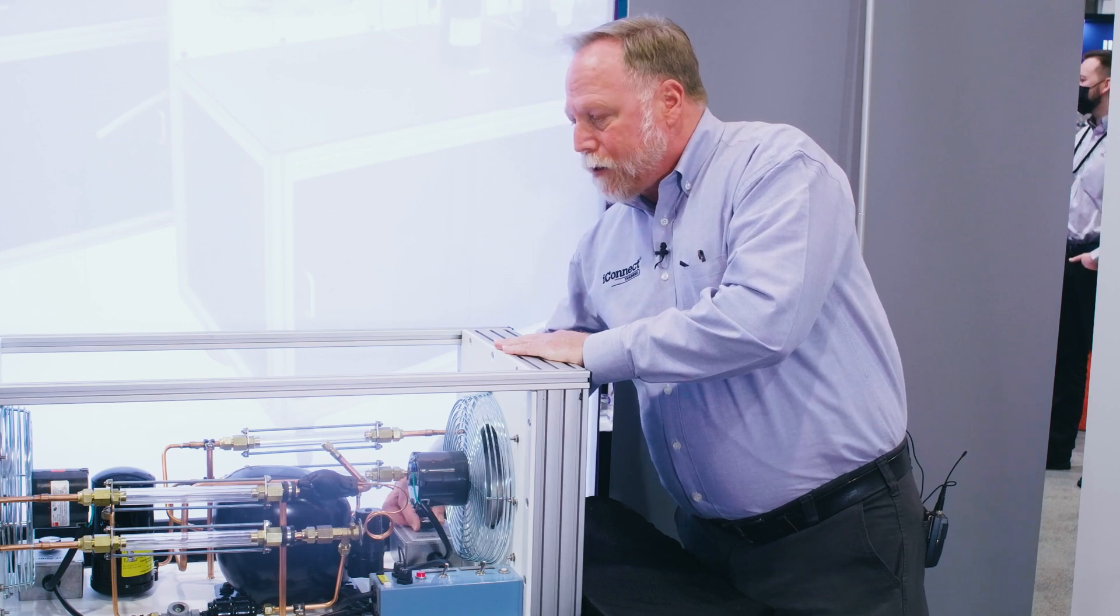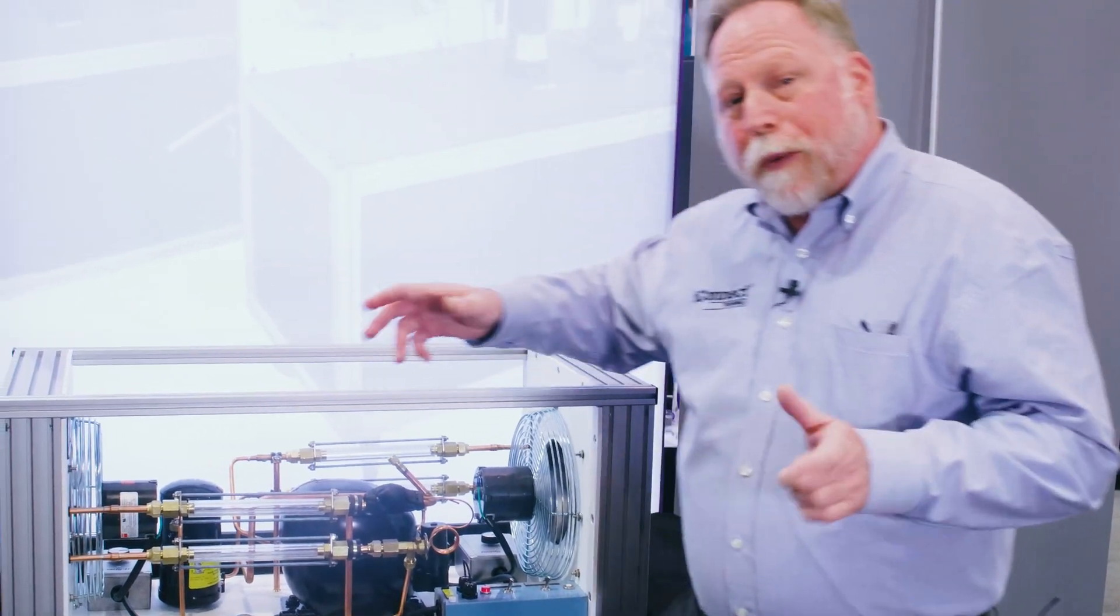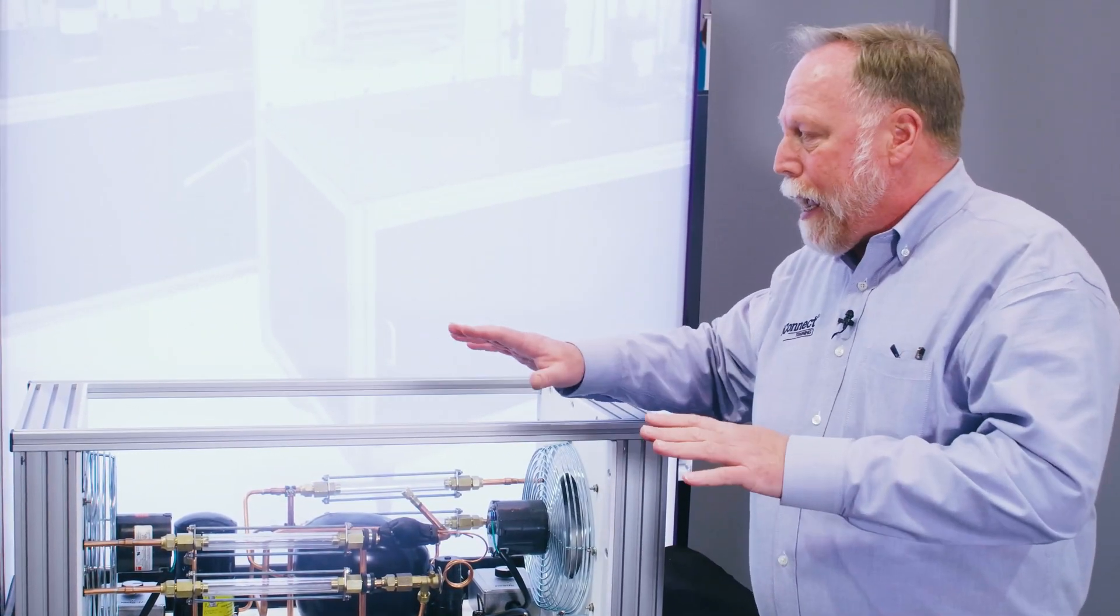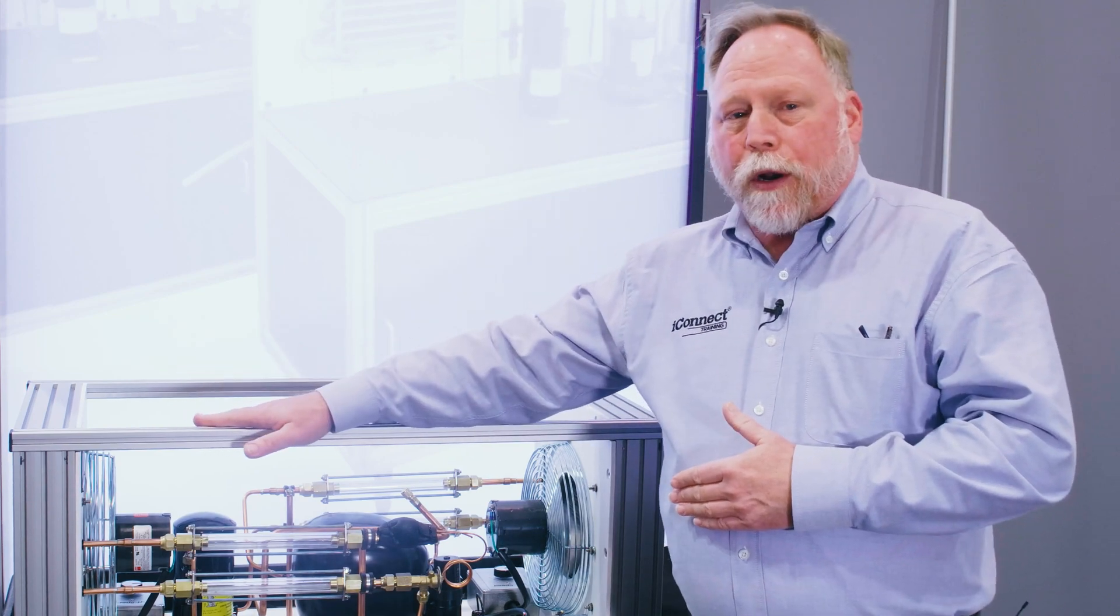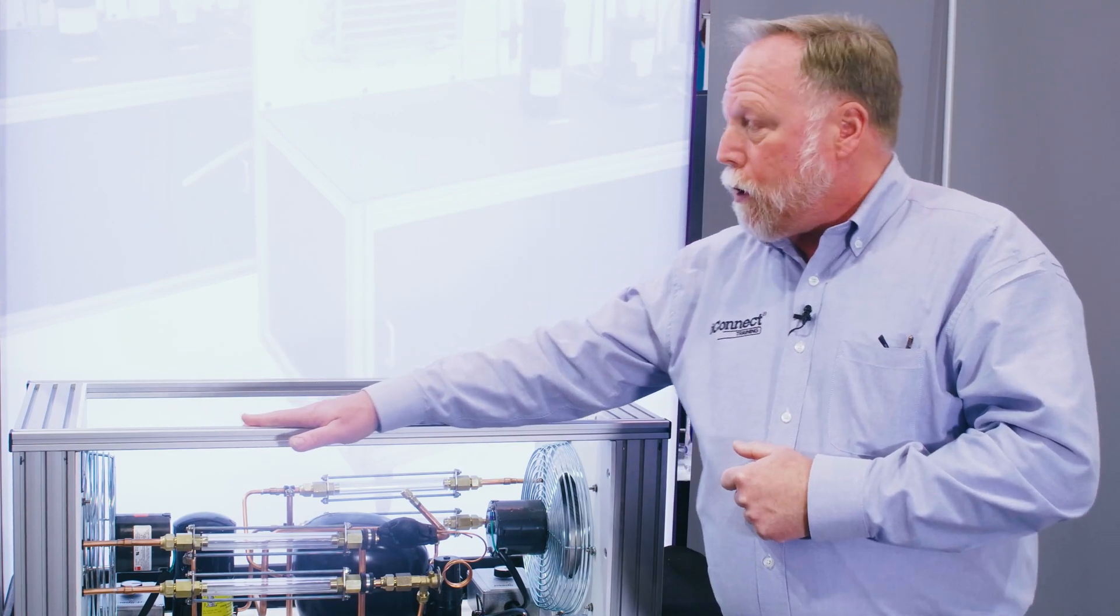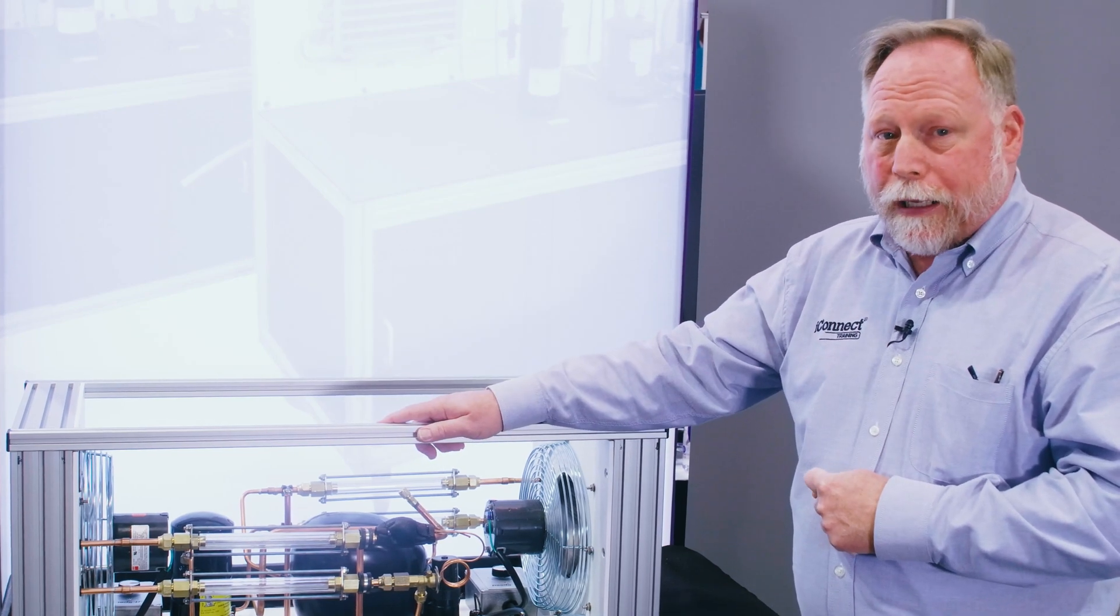What's really nice about this is because both these fans have variable speed control, you can create all kinds of different airflow scenarios, a dirty evaporator coil, dirty condenser, a completely stopped up filter, or what happens when we just lose the fan completely.